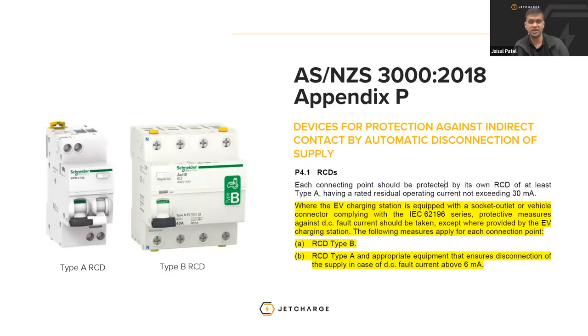So as I mentioned earlier, in section P4.1, each connecting point should be protected by its own RCD of at least type A, having a rated residual operating current not exceeding 30 milliamps. Where the charging station is equipped with a socket outlet or vehicle connector, protective measures against DC fault current should be taken, except where provided by the EV charging station. So if we do not have that fault protection, then we obviously need to apply for each connecting point an RCD type B or an RCD type A with appropriate equipment that ensures the disconnection of supply in case of a DC fault current over 6 milliamps. Next slide.